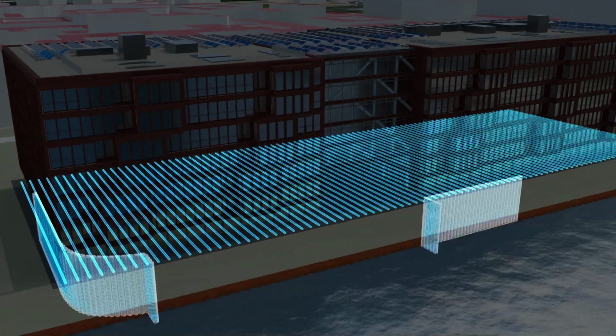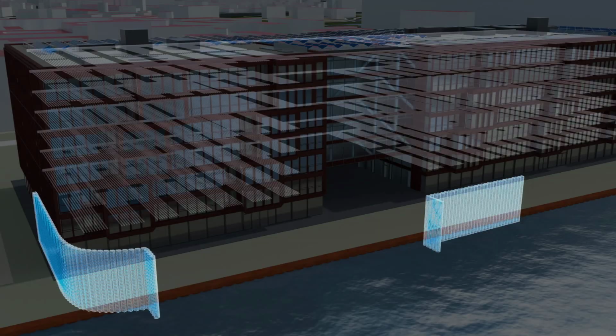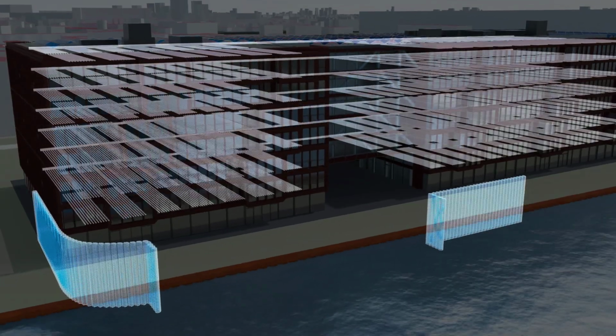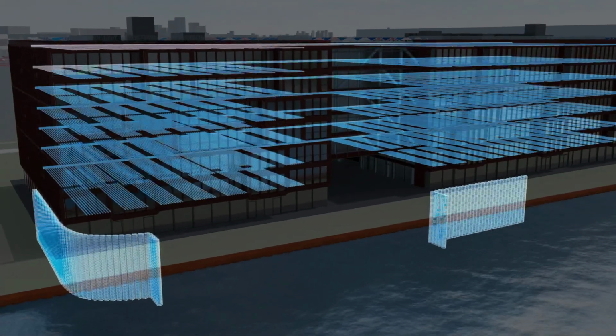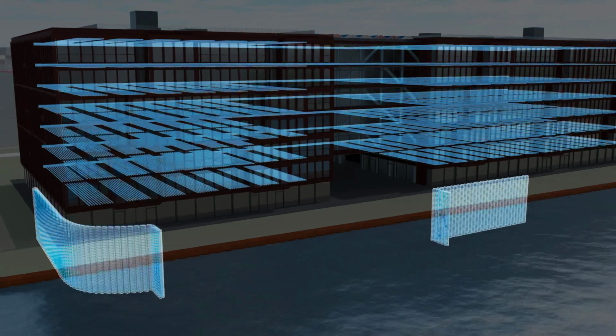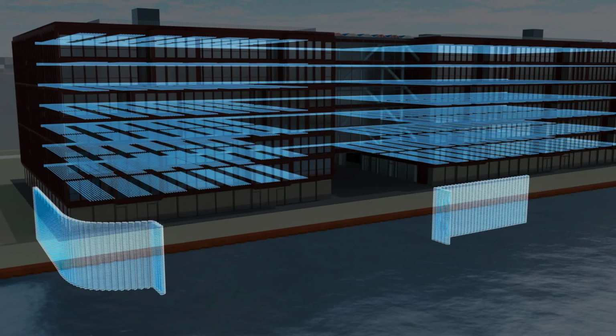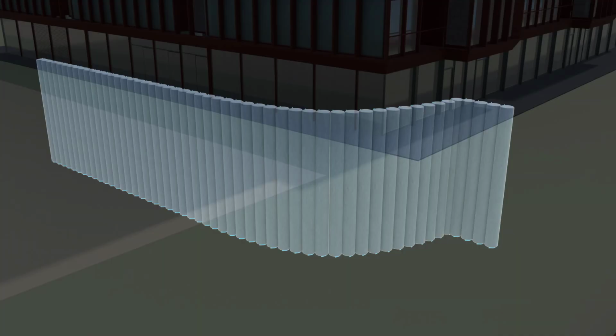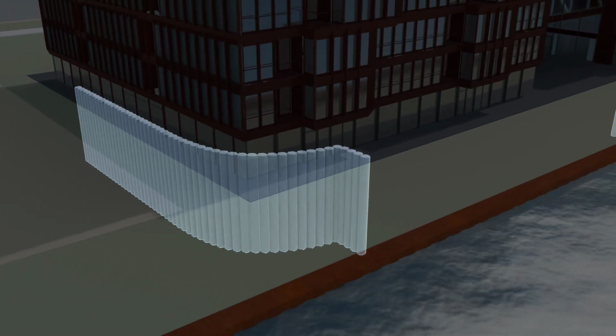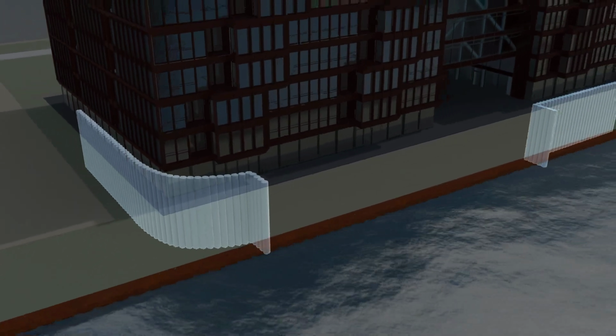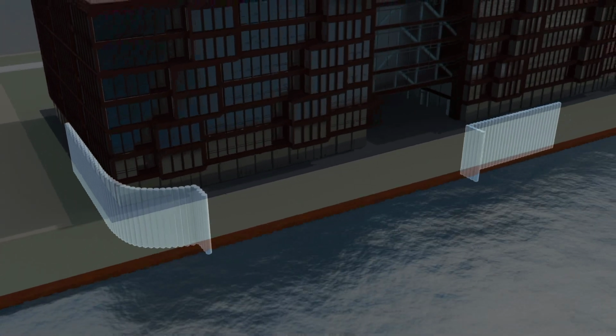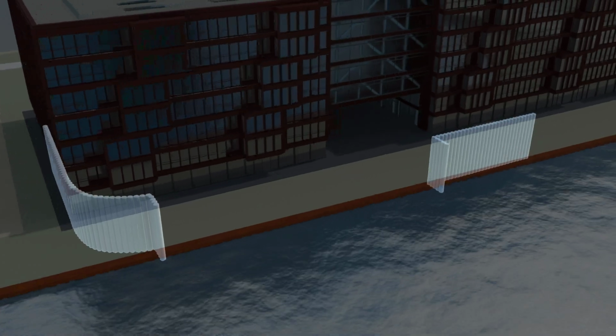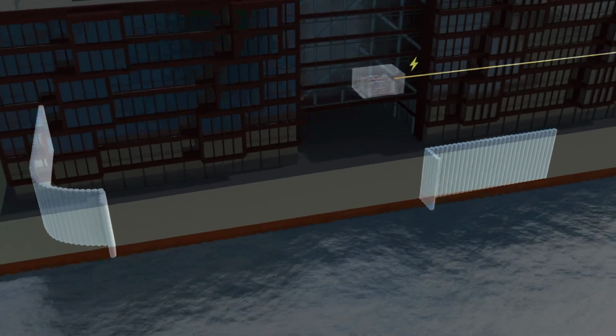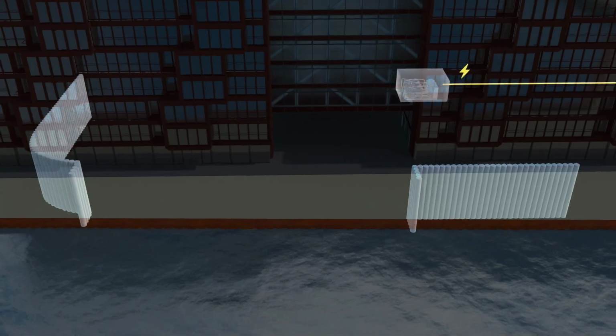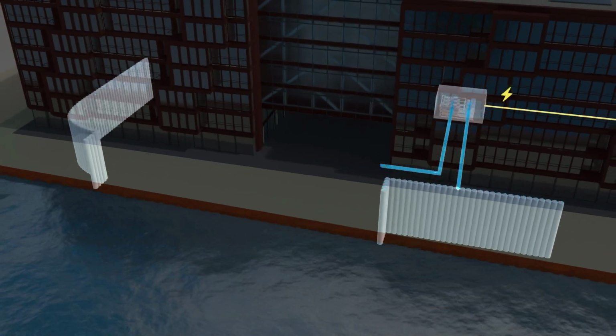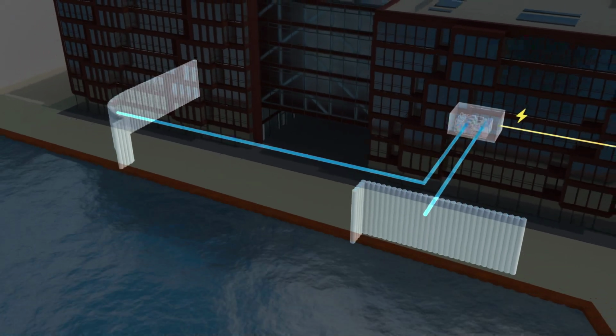If the water that had been stored below ground is below 15 degrees Celsius, the offices can be cooled directly via the radiant ceiling panels. After a few weeks, the bored piles and the ground under the building have warmed up to over 15 degrees. Direct cooling is now no longer possible. The heat pumps therefore cool the bored piles and the subsoil again during the night. During this cooling process, the heat pumps produce heat.